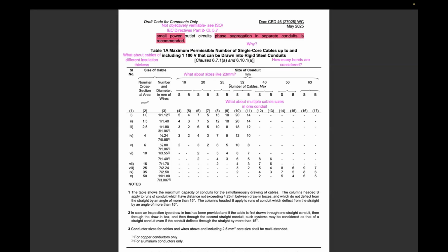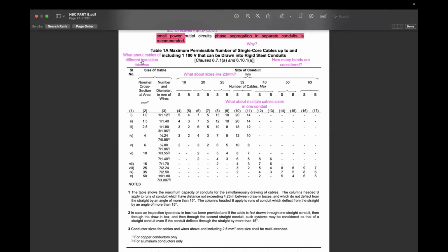Instead, what would have been much better, according to the performance principle, is if the NBC had simply said: fill factor of 40% shall not be exceeded for one bend, or 45% for one bend, fill factor of 30% shall not be exceeded for two bends, 15% shall not be exceeded for three bends. That way, it is up to the designer to figure out the fill factor, and one example could have been given. Instead of being prescriptive, a simple performance principle could have been provided that solves these issues of cable thickness, other sizes of conduit, multiple cable sizes, bends. This table on its own, as you can imagine, is not particularly helpful. Thank you.